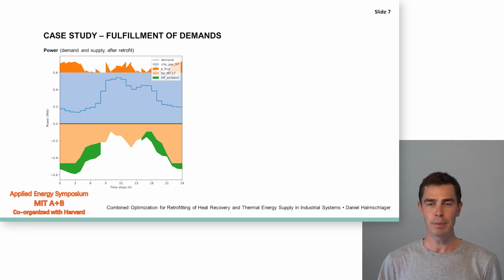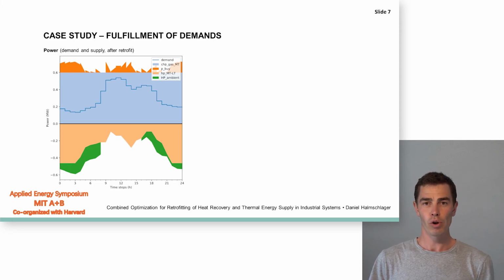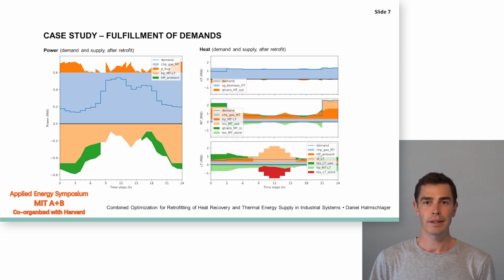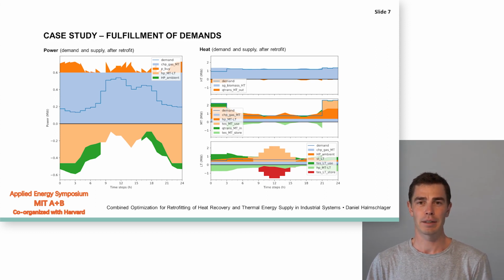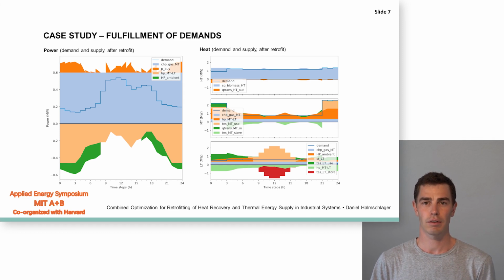For electric power, on the left side, we can see that the CHP plant can now run on full load, shown in light blue, for the full amount of time. And we can see that the heat pumps consume a large amount of electric energy outside of peak hours. For the heat demand, we see that the high temperature heat demand, the top part of the right chart, is only satisfied by the biomass-fired steam generator, as it is the only unit that can produce heat on this high temperature level. Excess high temperature heat is converted to medium temperature heat and used there.